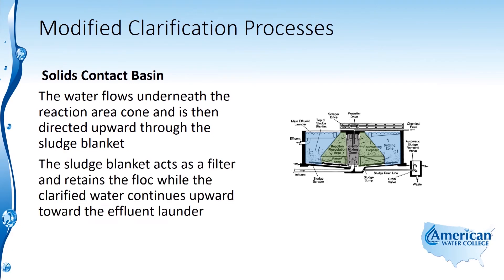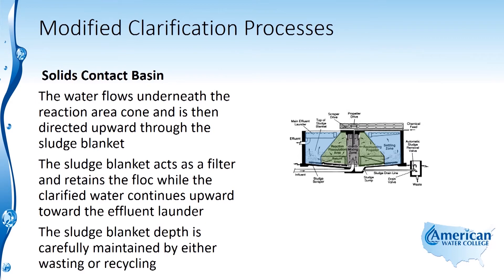The sludge blanket acts as a filter and retains the floc while the clarified water continues upward toward the effluent launder. The sludge blanket depth is carefully maintained by either wasting or recycling.